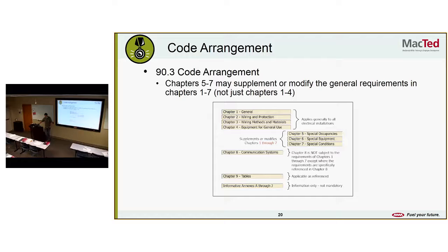They've changed up the code arrangement. It used to be Articles 5 through 7 were kind of special off on their own. They now may modify or supplement these other chapters. So when you look at the NEC, the way it's broken down, there's general wiring methods, equipment. They have these extras off to the side now, 5, 6, and 7, that can modify. So if you're doing a project, be sure to check those for special circumstances because they may overwrite rules in the main code book. There's so many different systems out there now, they have to have special sections that can overwrite. Kind of like the HVAC can overwrite the NEC in Washington.